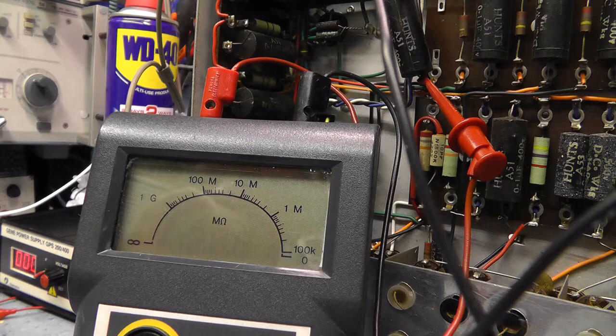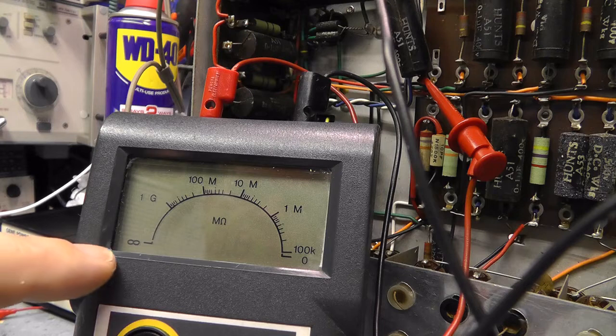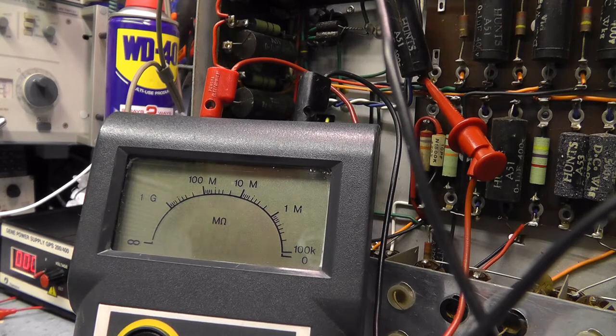So if you've got a piece of equipment that isn't earthed and you're suspicious the chassis is live, you connect one lead to the chassis and one to the live socket of the wall socket, with the unit turned on, press test, and you should get basically an infinite resistance reading—meaning there's no connection between the incoming primary and the chassis of the unit.